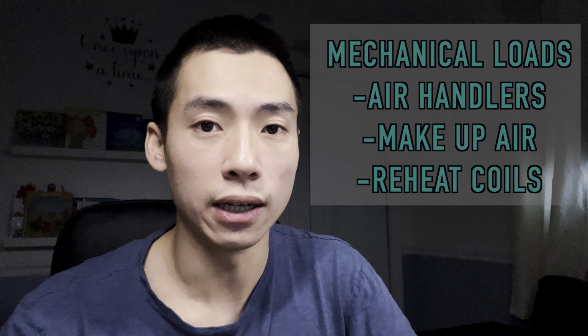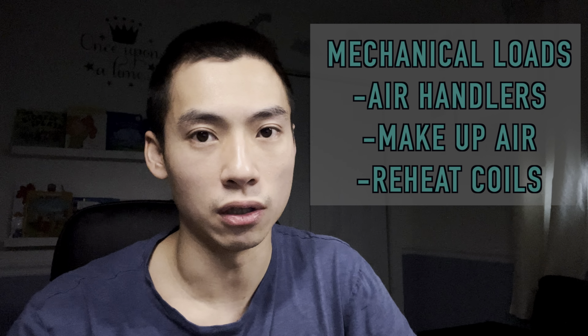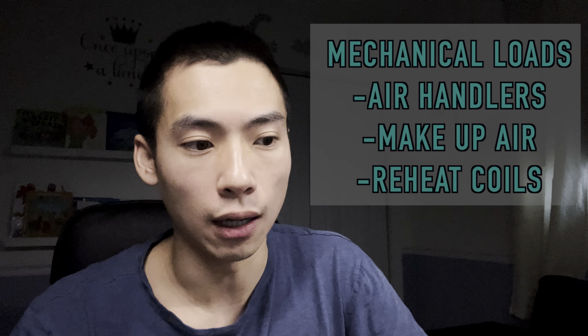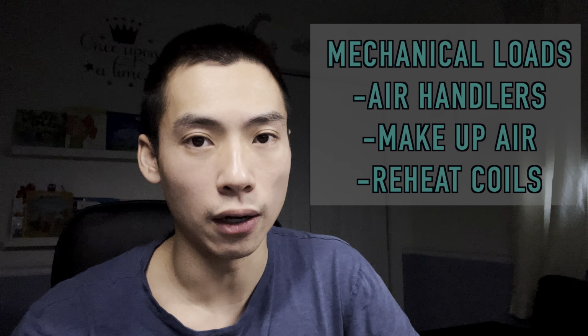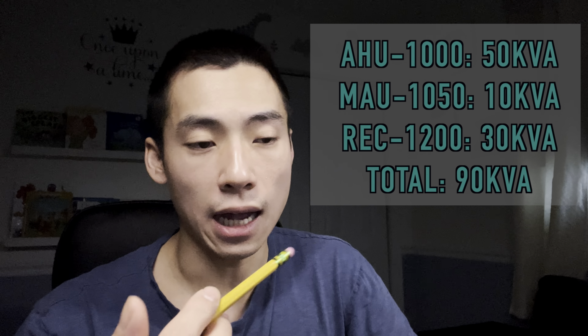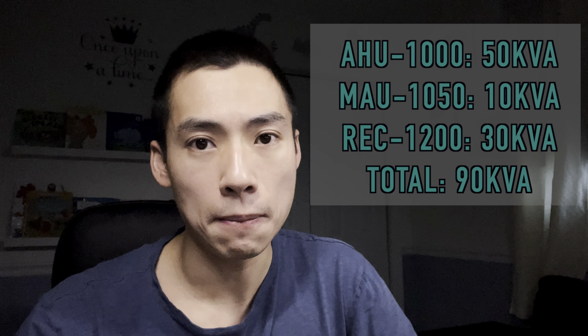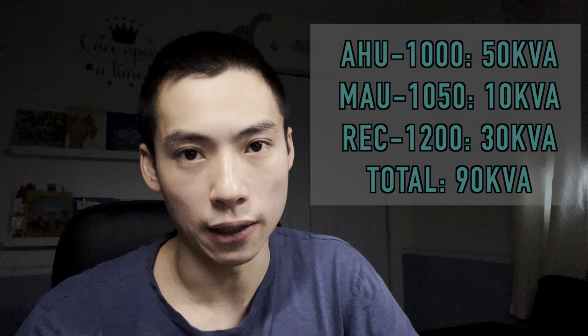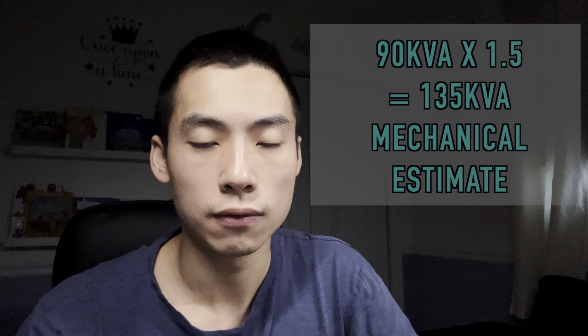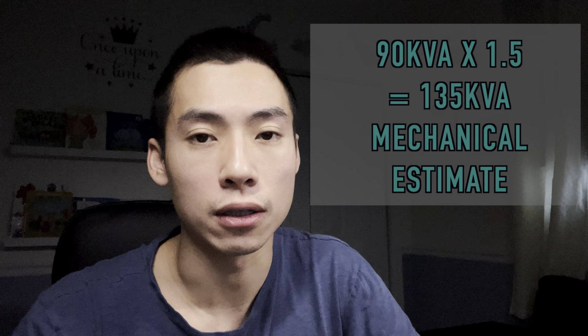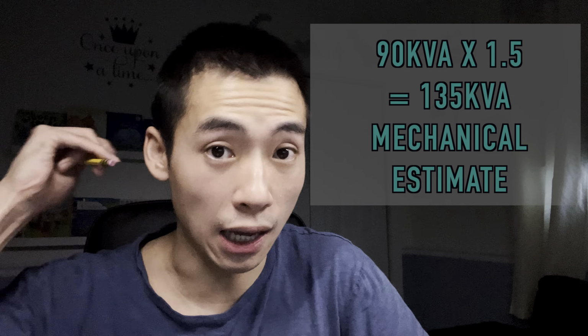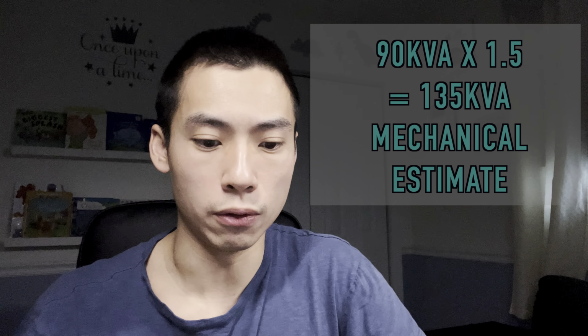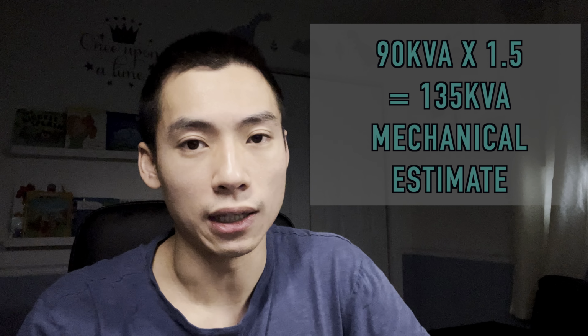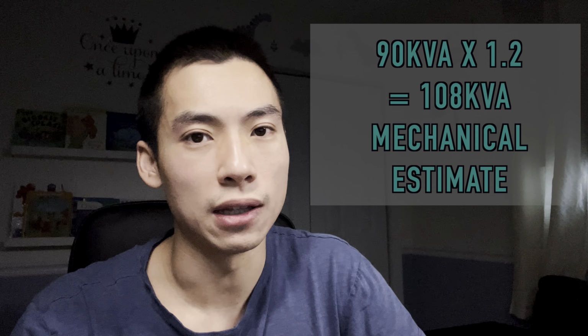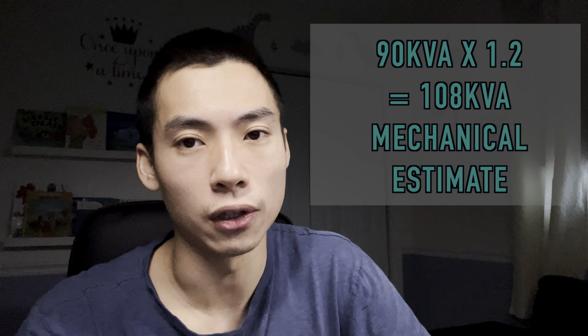So the first step is I would ask mechanical to see what kind of equipment, if they have an approximation of horsepower or tonnage. And from there, I would list all their equipment, add them up into kVA, and then maybe apply, I don't know, a 20 to 50% fluff factor to it. So as you're getting closer to the end of your concept or basis of design, you can probably bring that down to like 20%, I'd say your minimum. Yeah, give yourself a little bit of room.